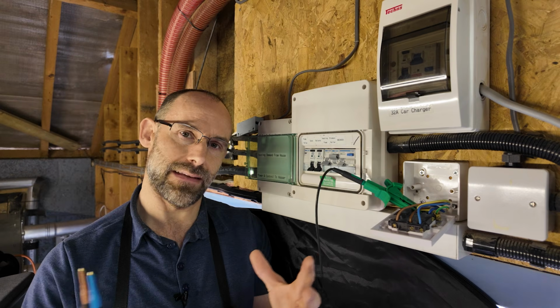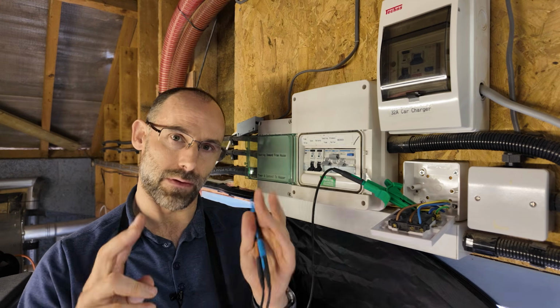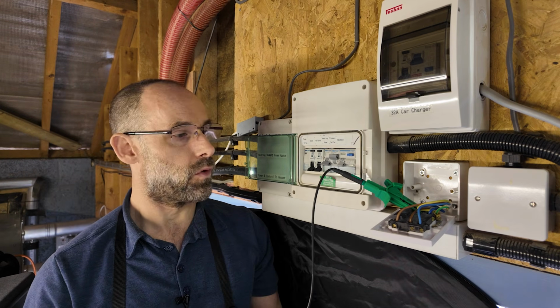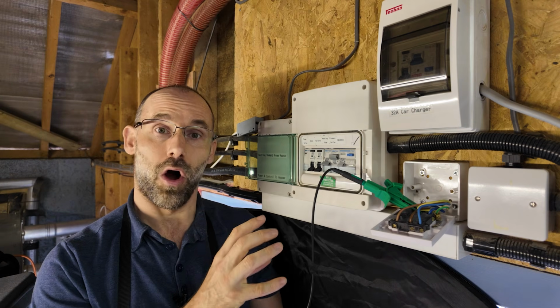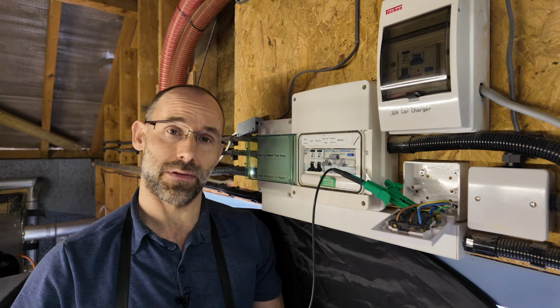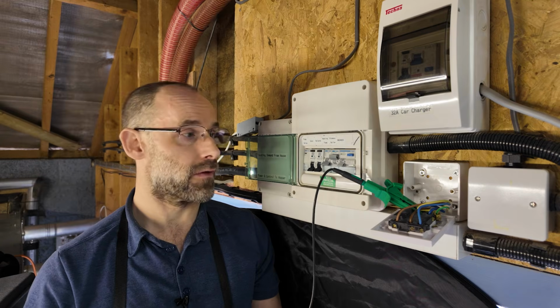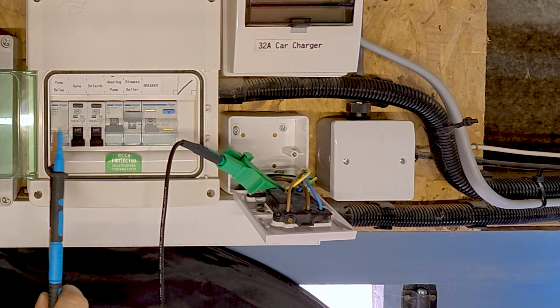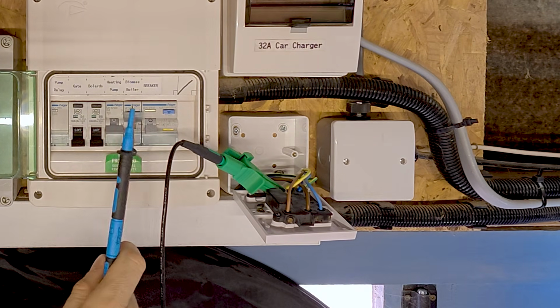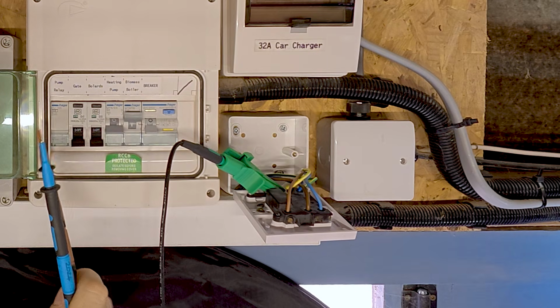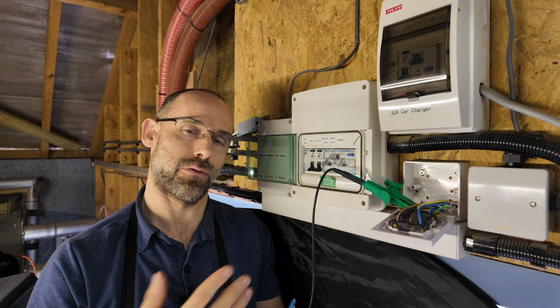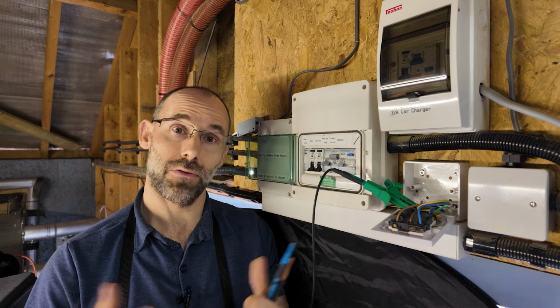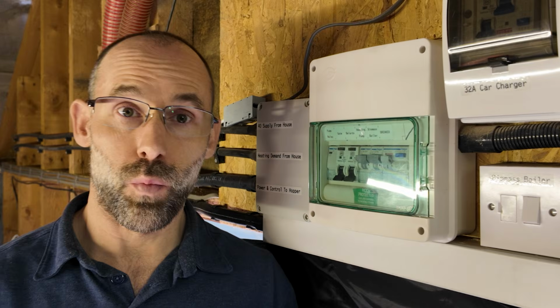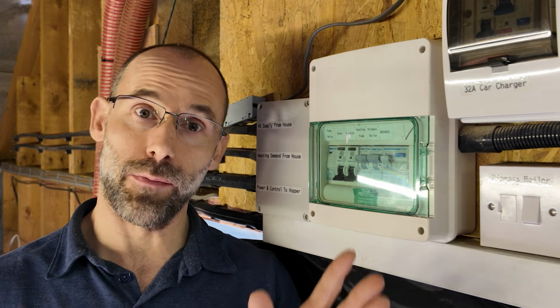Now I would actually repeat this test a couple of times at something called a different phase, but for simplicity, we'll just show you there's an overview of testing an RCD with a proper testing meter to make sure that it works. And that will apply in this particular case to all of these circuits on this board because this one RCD protects all of these different circuits. You might need to repeat that test for every single circuit depending on what's going on. So RCD check, done.